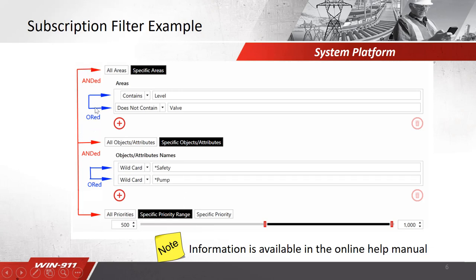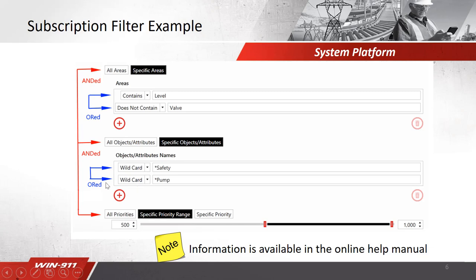Inside here, the blue items are ORed, so in this example we will be looking for something that has an area that contains the word level or does not contain valve, and has a specific object attribute area that is safety or pump. Notice the wildcard feature here, we're using the asterisk for a wildcard for anything before that. Finally, we'll be including anything that includes the specific priority range between 500 and 1000.